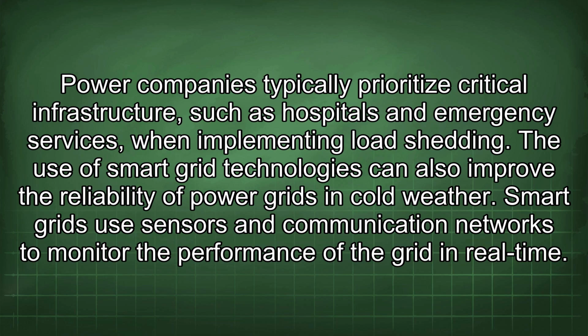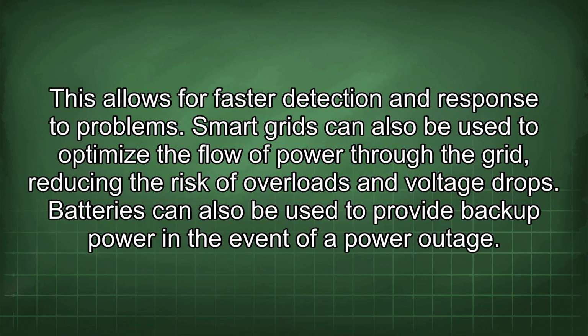The use of smart grid technologies can also improve the reliability of power grids in cold weather. Smart grids use sensors and communication networks to monitor the performance of the grid in real time. This allows for faster detection and response to problems. Smart grids can also be used to optimize the flow of power through the grid, reducing the risk of overloads and voltage drops. Batteries can also be used to provide backup power in the event of a power outage.